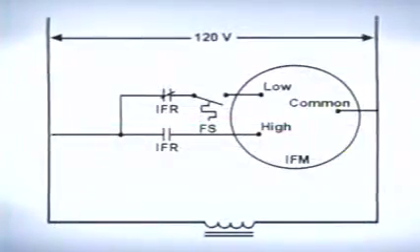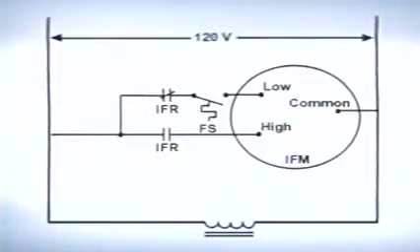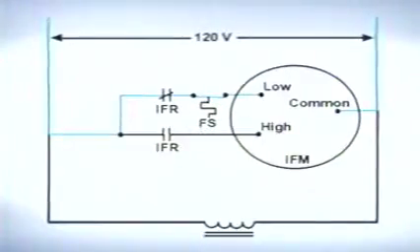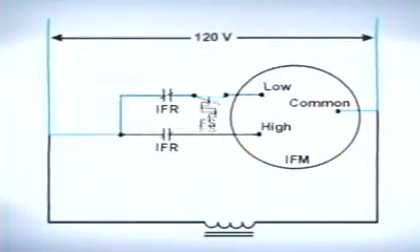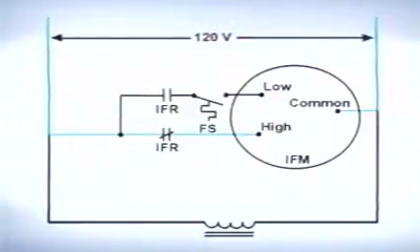Relays can also be used to change the speed of a fan motor depending upon the system's mode of operation. In the schematic shown here, the indoor fan will operate at low speed during the heating mode and at high speed when operating in either the cooling or fan only modes.